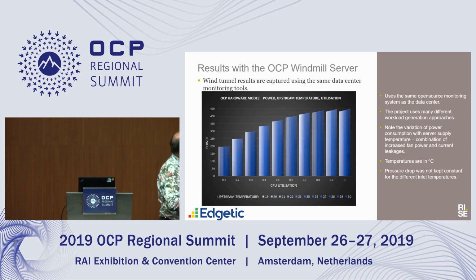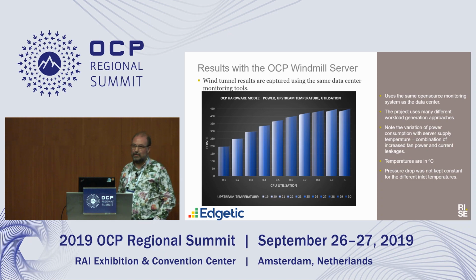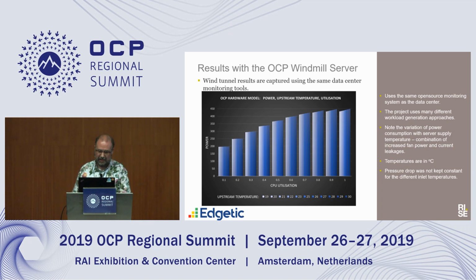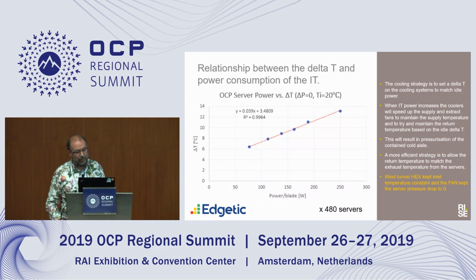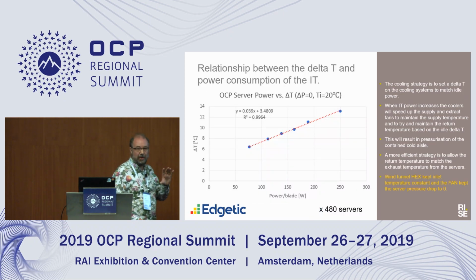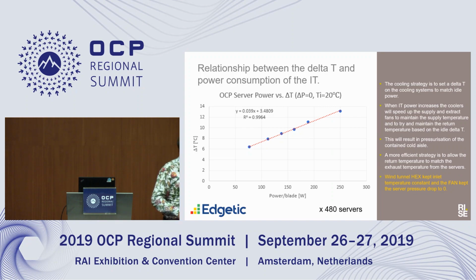As you increase the load on the CPU—this is percentage of CPU utilization for one of the servers—you can see that depending on the input temperature, up to 30 degrees, there's a difference in power draw. You could say that's the fans, and it mostly is, but some is also current leakage as you increase the CPU temperature. So the fans do consume quite a bit of energy, and when I get to the holistic cooling control in a minute, you'll see how much.